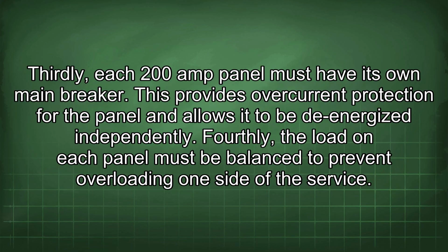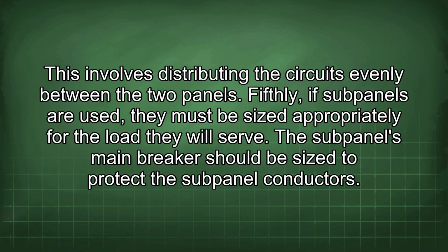Thirdly, each 200 amp panel must have its own main breaker. This provides overcurrent protection for the panel and allows it to be de-energized independently. Fourthly, the load on each panel must be balanced to prevent overloading one side of the service. This involves distributing the circuits evenly between the two panels.